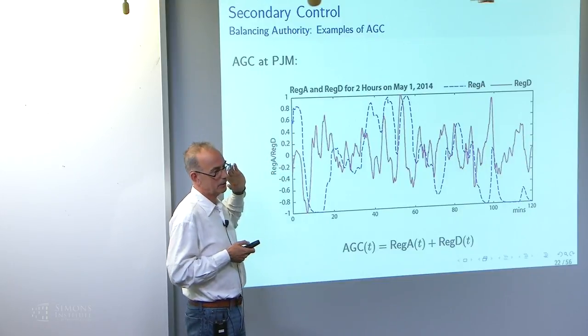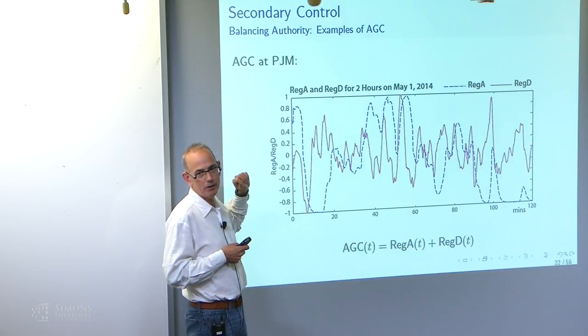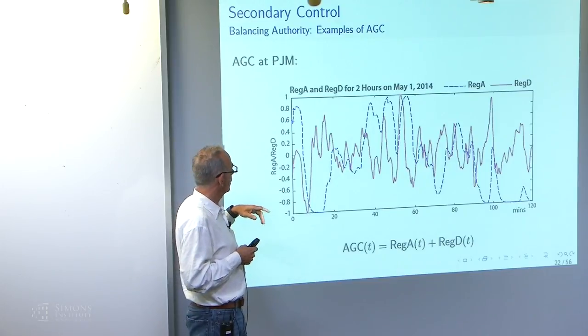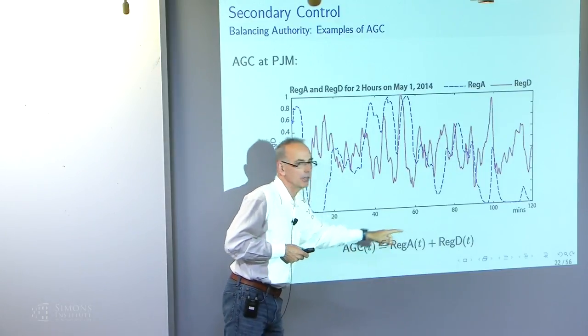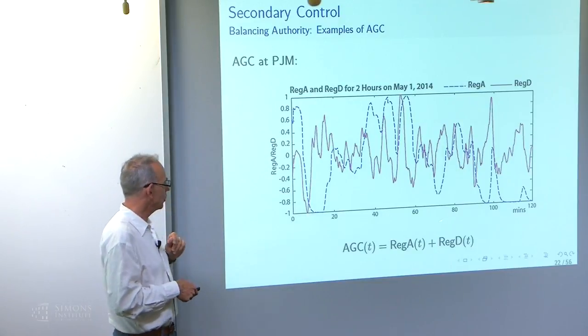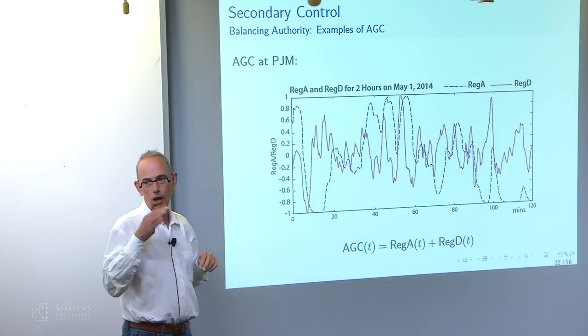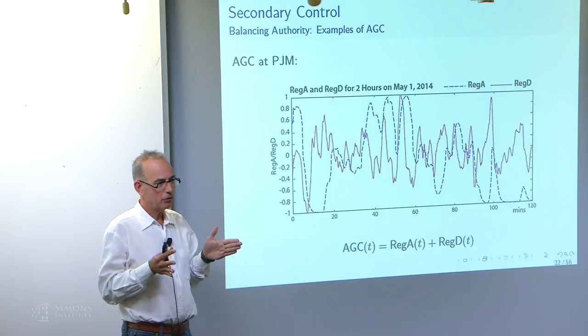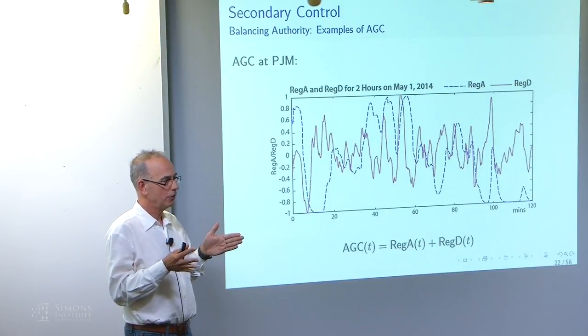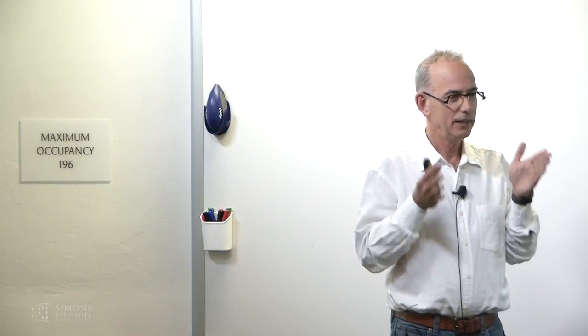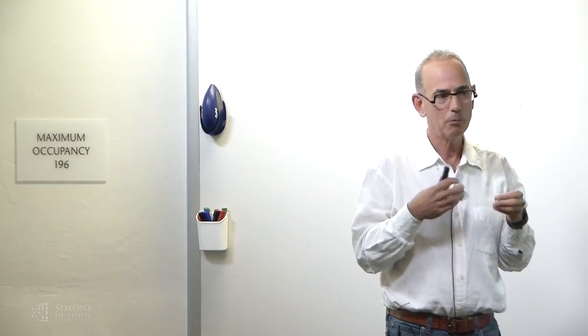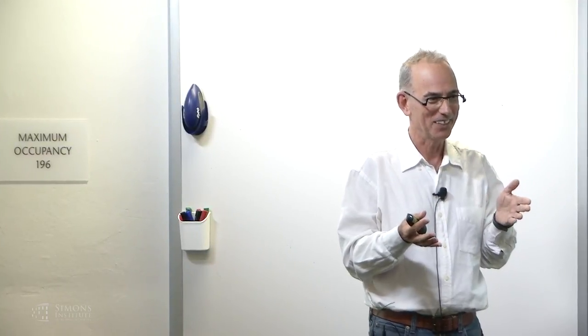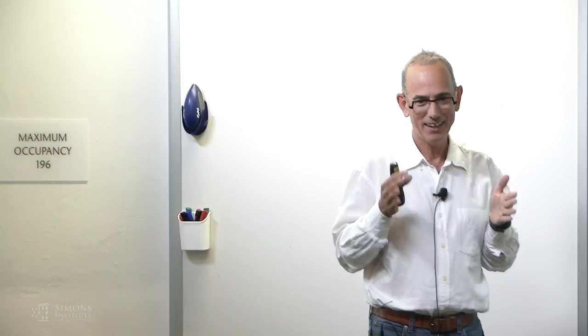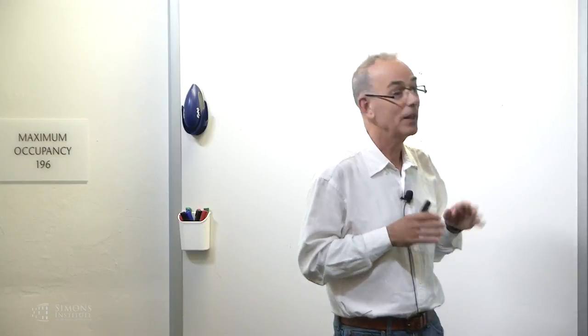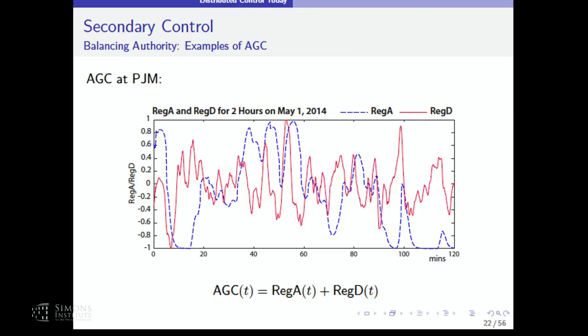And this is what it looks like. In PJM, on the East Coast, what they do is break it into two parts, which I think was a brilliant move. They have what's called Reg D, the dynamic regulation, which is higher frequency content and way more constrained in terms of energy—if you integrate the energy over 10 minutes or an hour, it's zero. They do that because they send these signals to batteries, which have energy constraints: they can go up and down, but can't produce energy, or they have losses, and the batteries have to take care of their own losses. If they have losses, they have to buy energy. So Reg D is exactly zero mean.